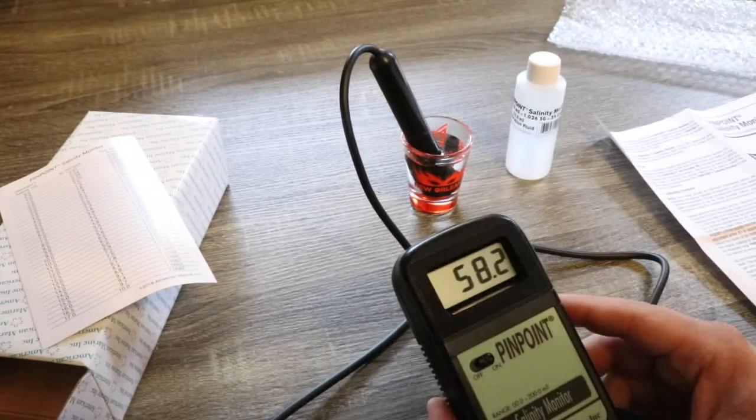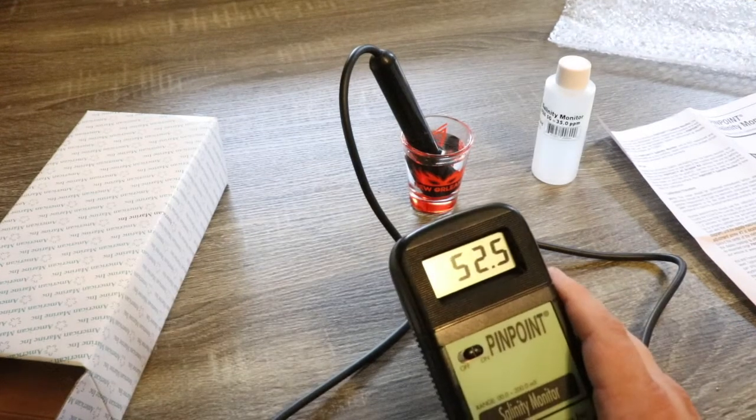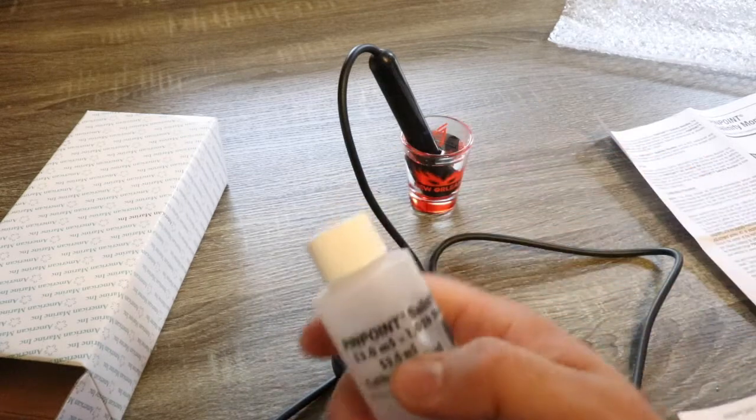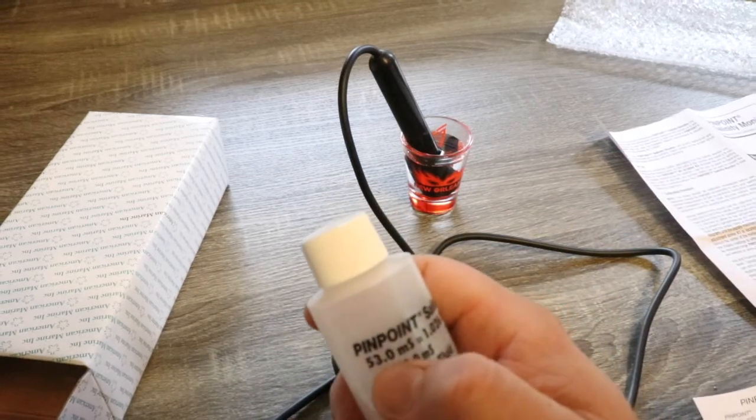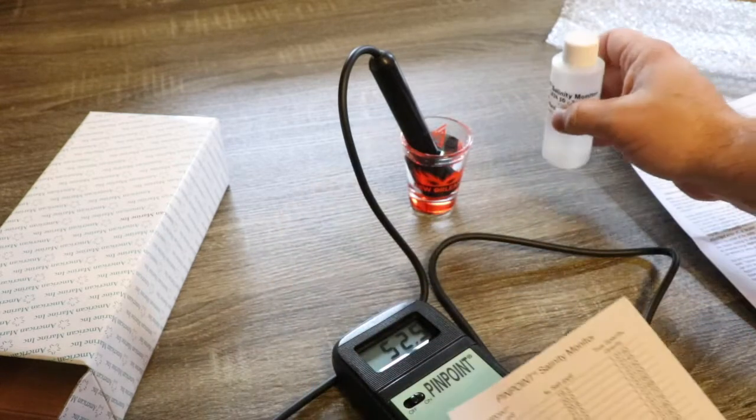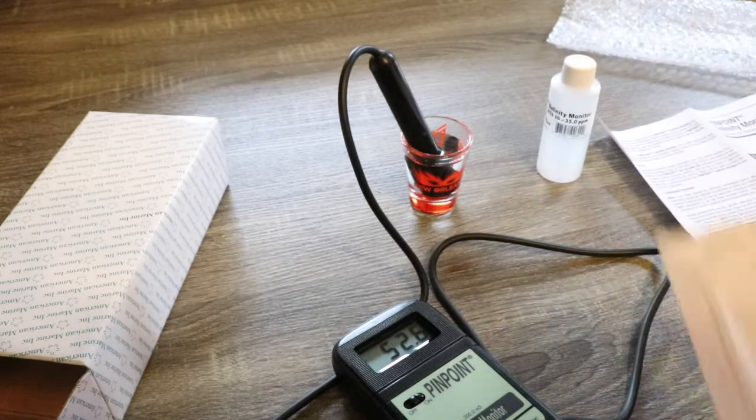We're going to turn it on and let it do its thing for a little bit. It's measuring 52.5, so our calibration fluid, which is what it's sitting in, should be at 53.0, which is going to give us the 1.026 specific gravity. This is still kind of moving around a little bit, so we're going to give it a couple more minutes just to hit that perfect temperature, and then we're going to go in the back and adjust this to the 53.0.